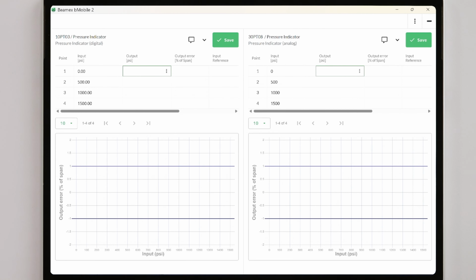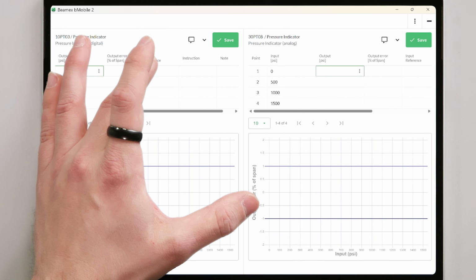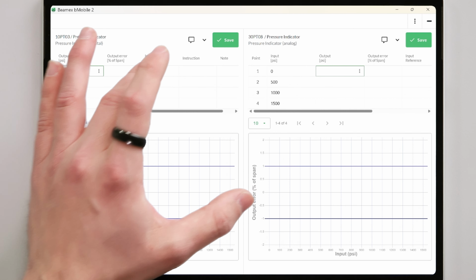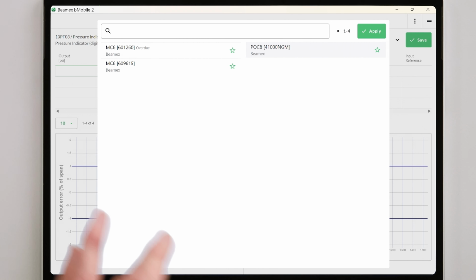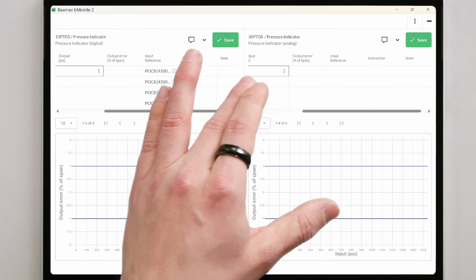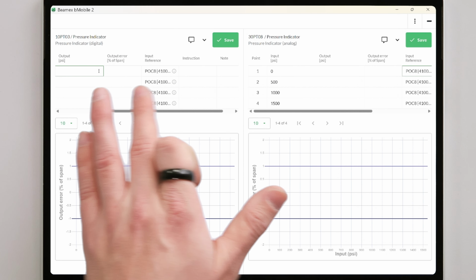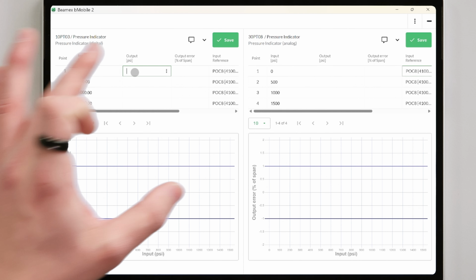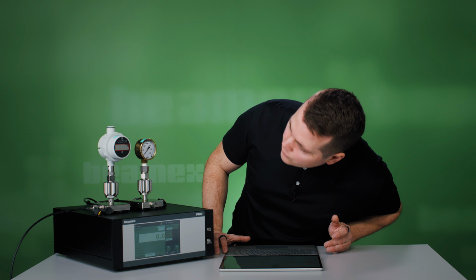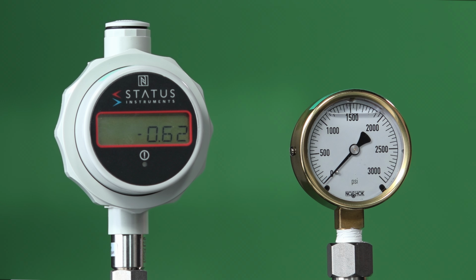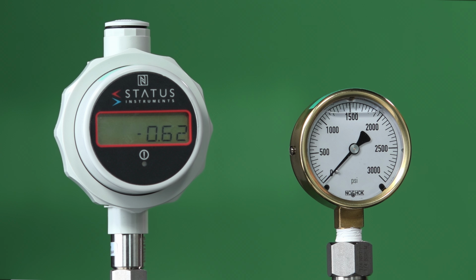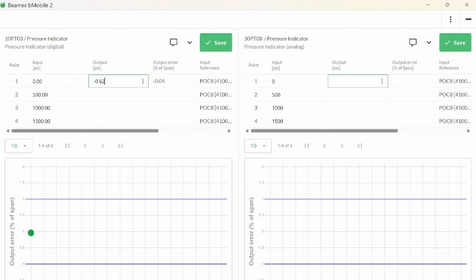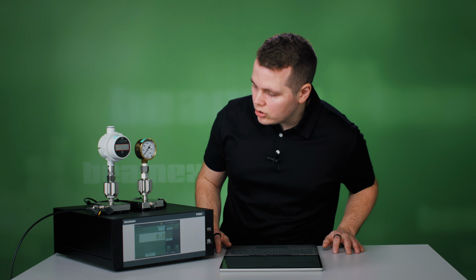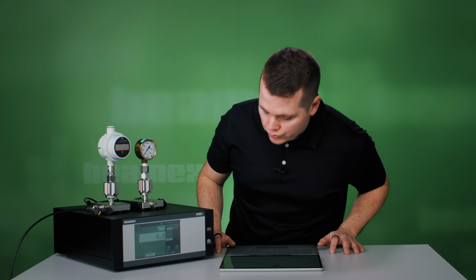Before I start the calibration, I will have to select my input reference. So I'll click over here in input reference. I'm using the POC 8 as the reference. Apply. Same thing for the other one. So now bMobile knows what the reference I'm using is, and we can start the actual calibration. So the first calibration point is at 0. Let's see where we're at. Yep, we're at 0. The digital reads minus 0.62. Then on to the analog one, which reads a flat 0.